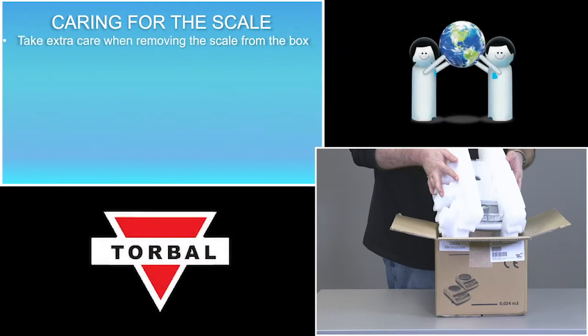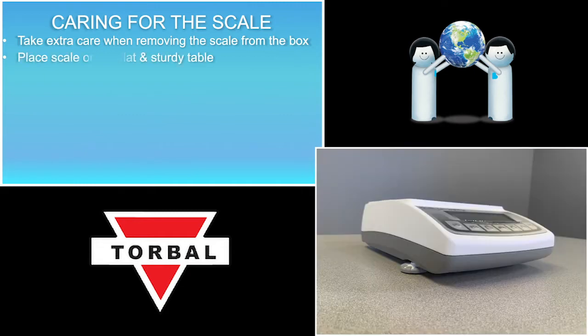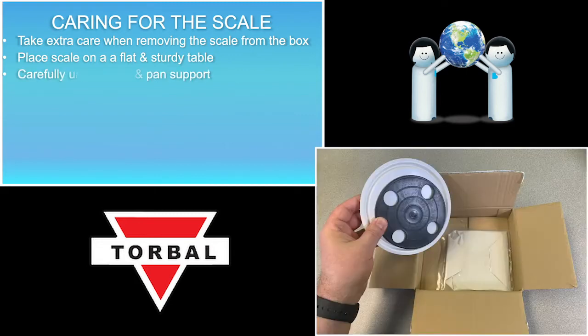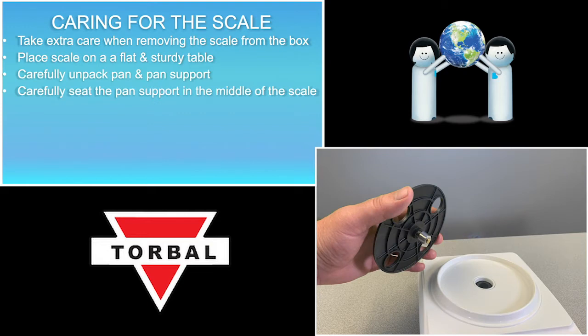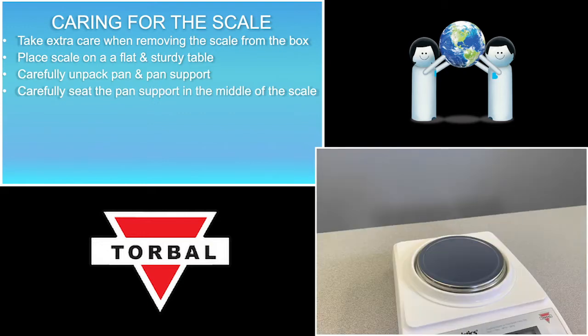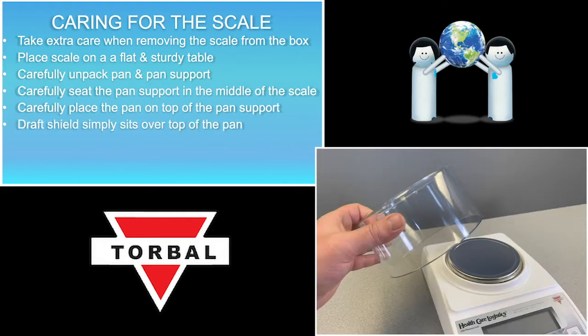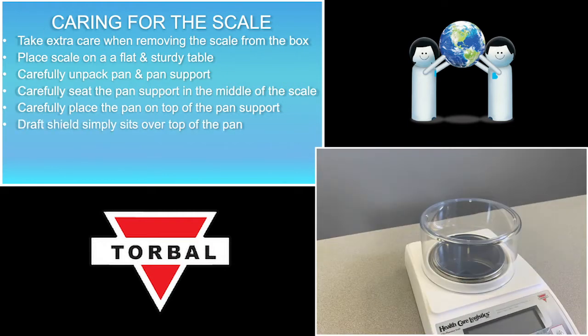Before we begin, let's take a moment to discuss caring for the scales. The internal mechanisms are extremely sensitive, so make sure you take great care removing the scale from the box. Make sure the scale is placed on a flat, sturdy table. Unpack the pan and pan support. Carefully seat the pan support in the middle of the scale, then place the pan on top. If you purchase the optional draft shield, it simply sits over top of the pan.